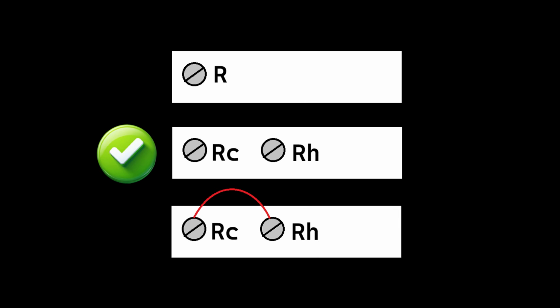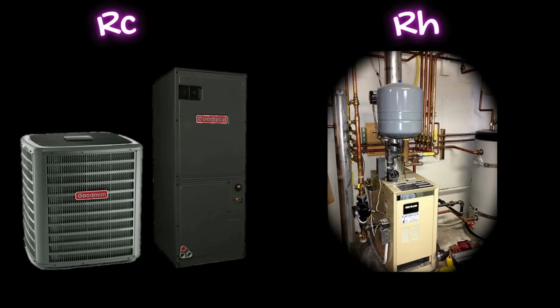Most new thermostats come with separate RC and RH terminals, and what this is telling you is that the thermostat is capable of controlling two completely different systems, each one with its own transformer. An example of this would be your cooling system is an air handler and an outdoor condensing unit, while your heating system is a hydronic boiler or a steam boiler.